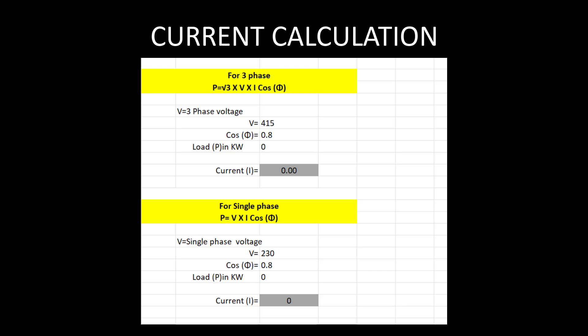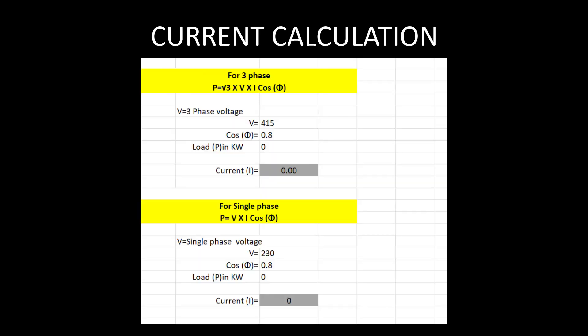To find the current rating, an Excel sheet has been prepared and can be downloaded from the description. For a three-phase system, the power equation is P = √3 × V × I × cosφ, where cosφ is the power factor and V is the standard three-phase voltage. For a load of 30 kilowatt, entering 30 in the Excel sheet gives a load current of 52.23 amps.